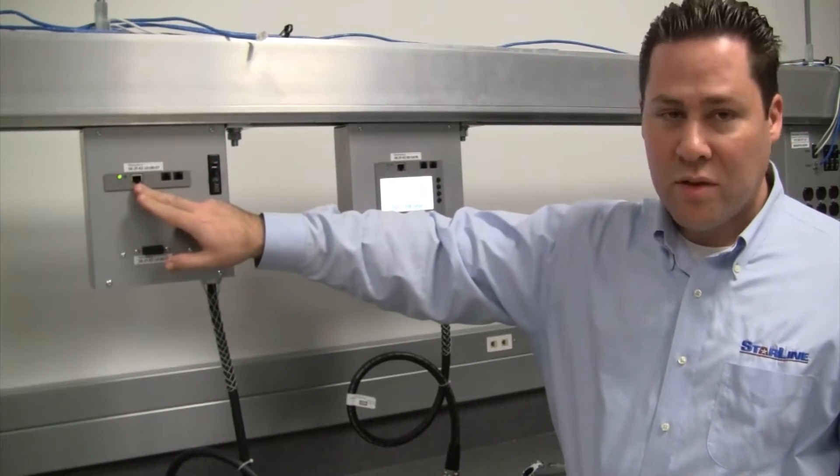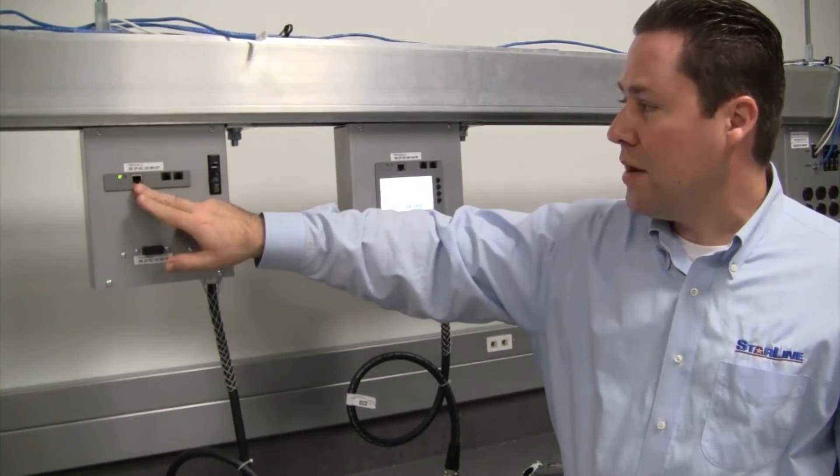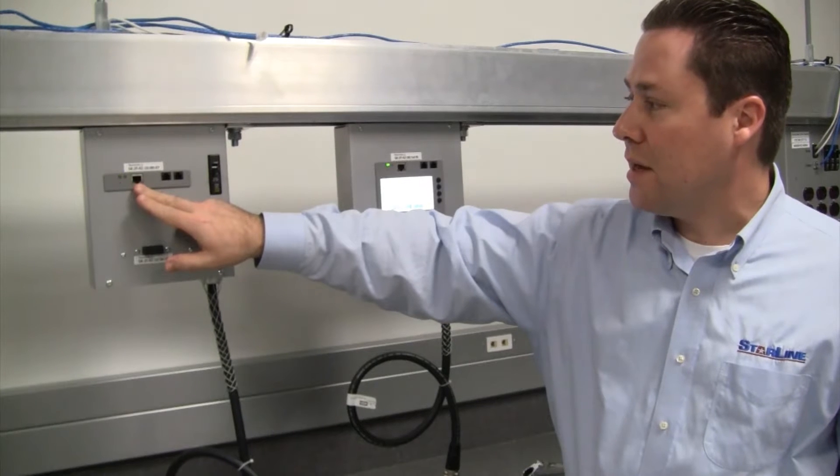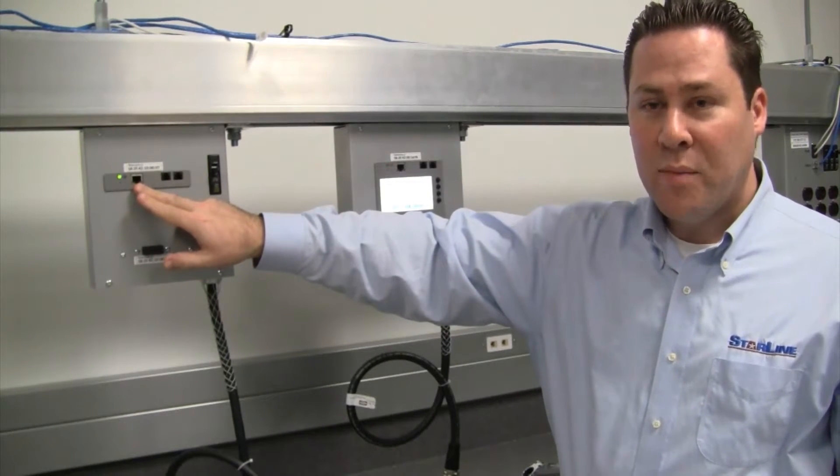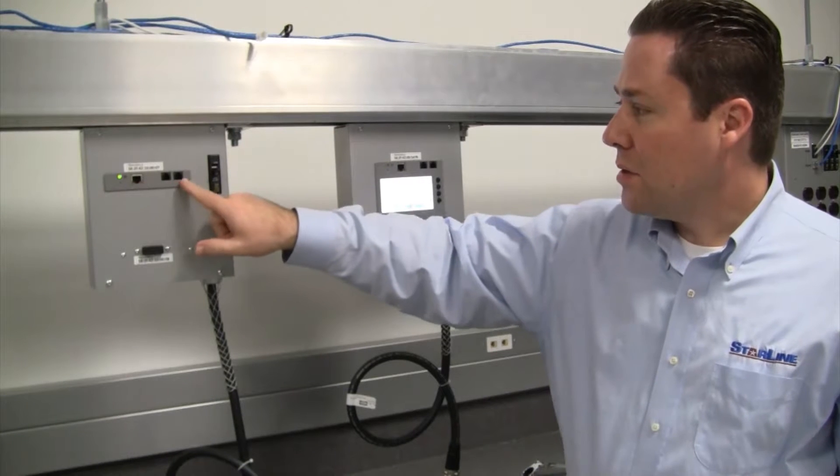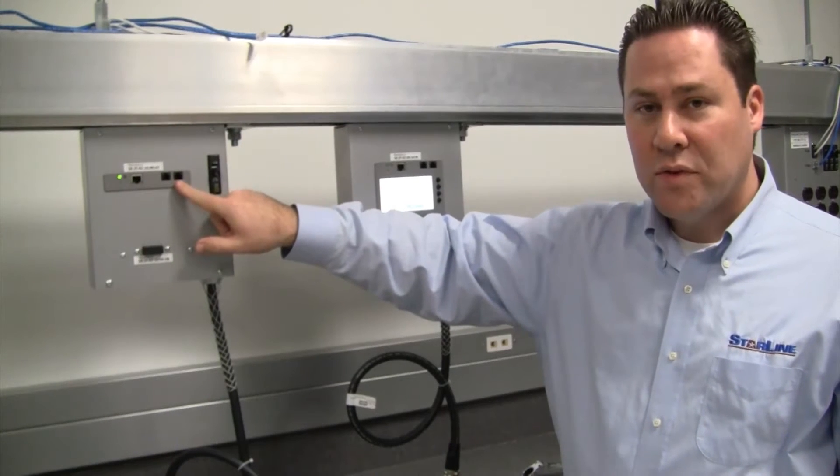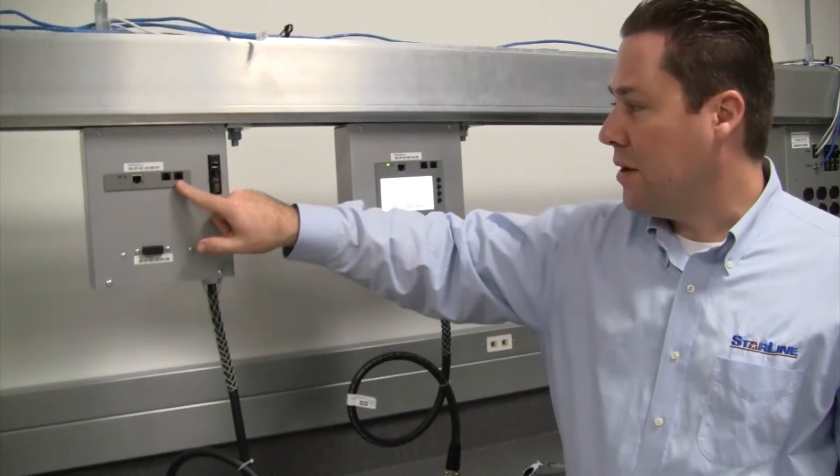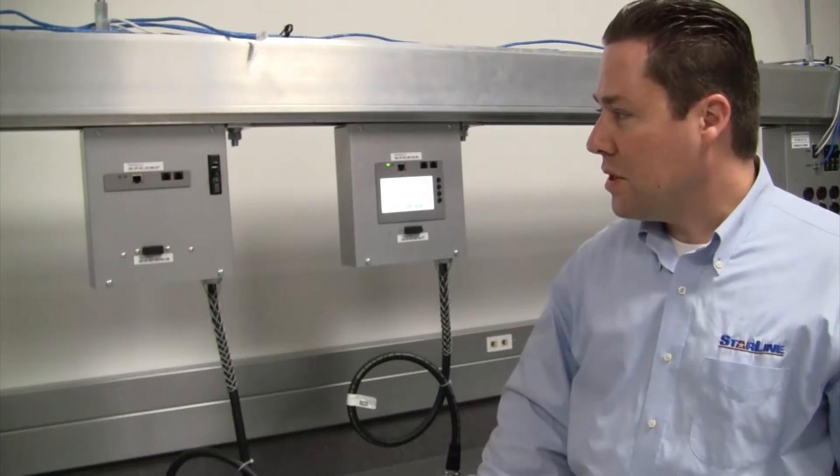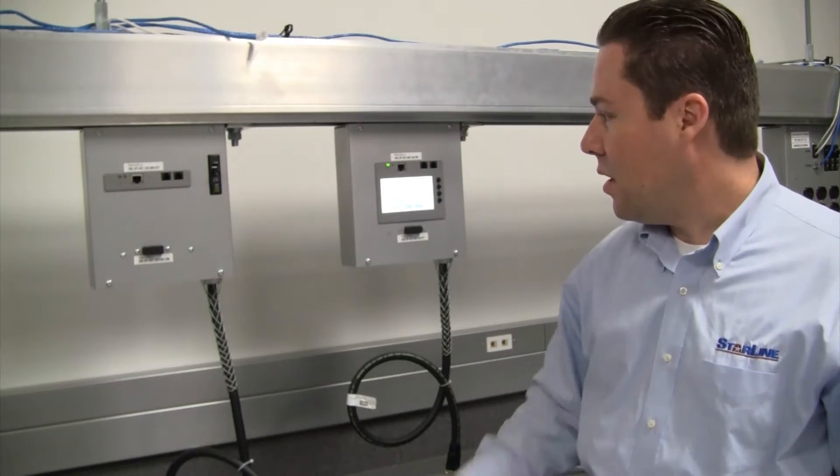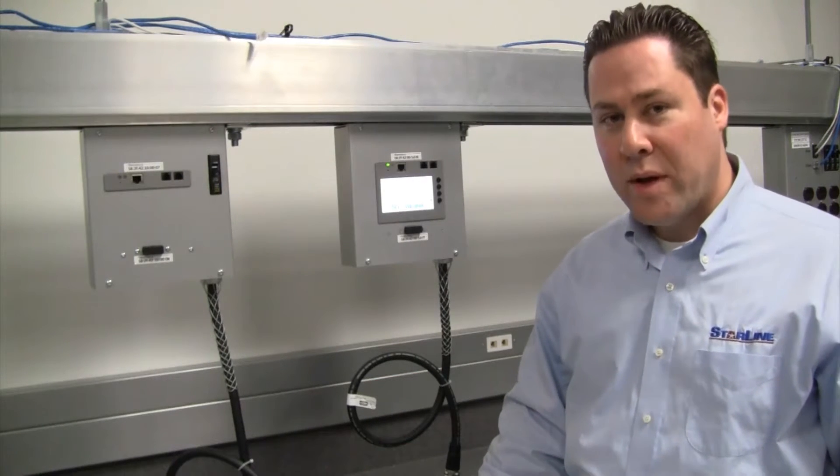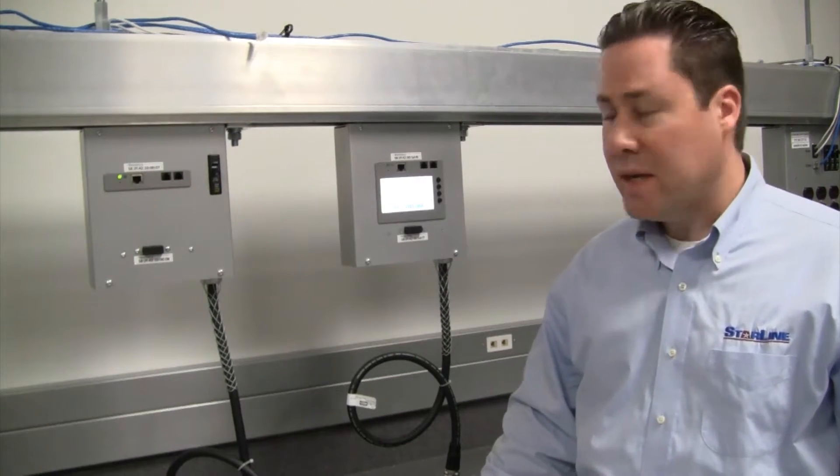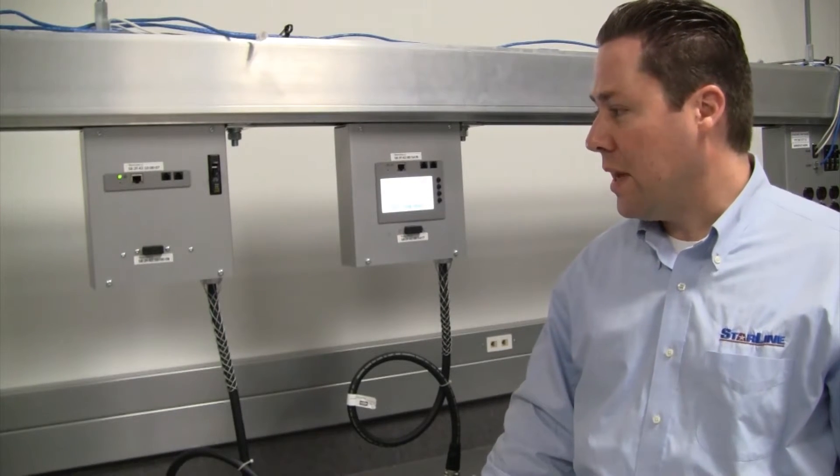So we have an Ethernet port here, standard RJ45 jack, which can communicate both SNMP and Modbus TCP. You also have two RJ11 jacks for Modbus RTU. We'll talk about the provisioning of those and how you actually log into the integral web page to set the settings up for both of those protocols.